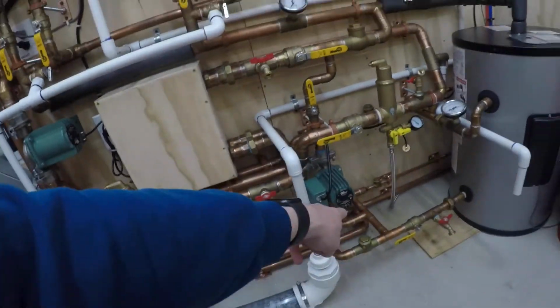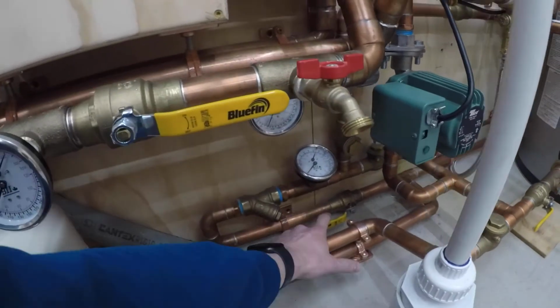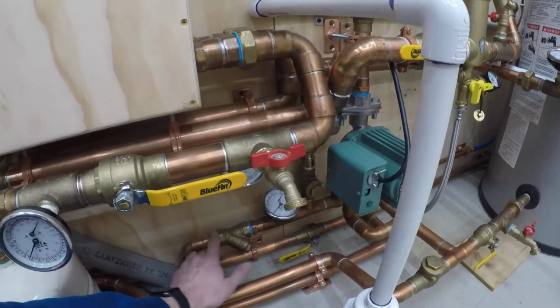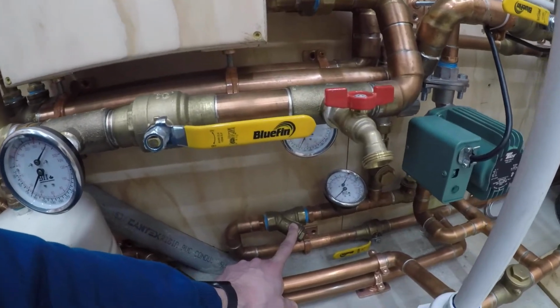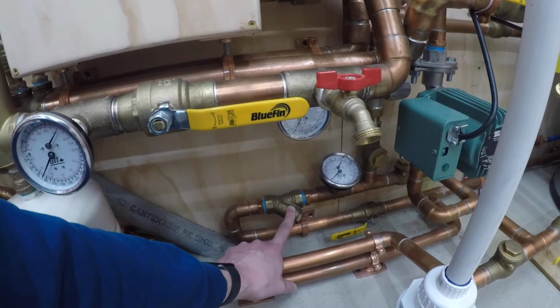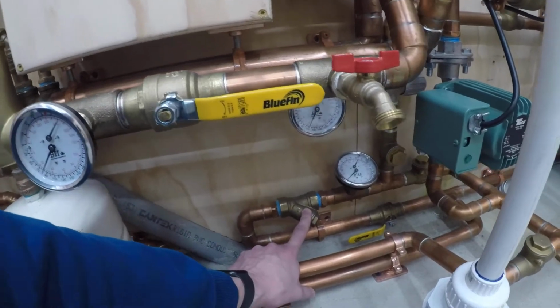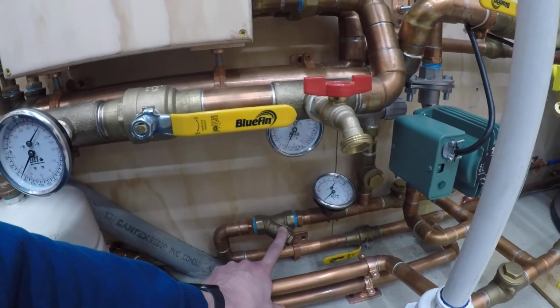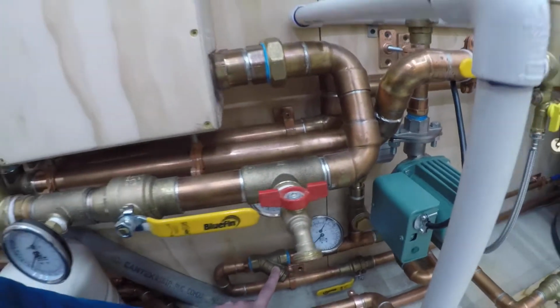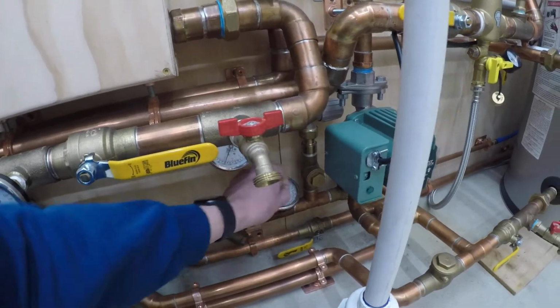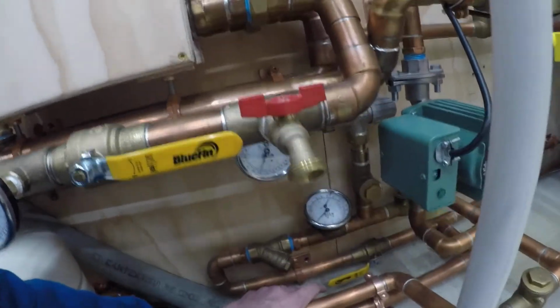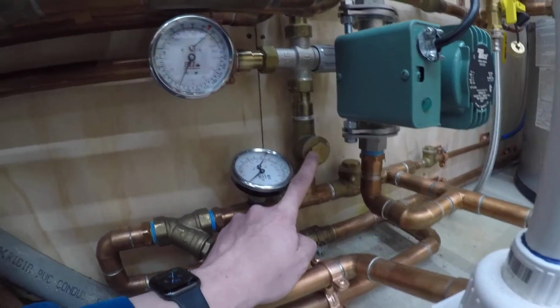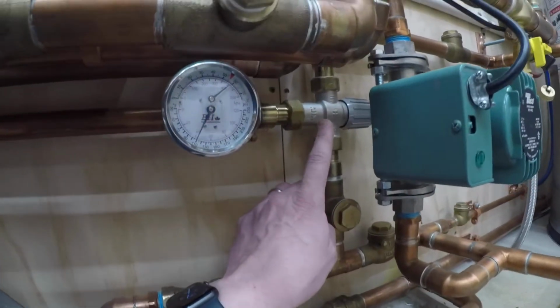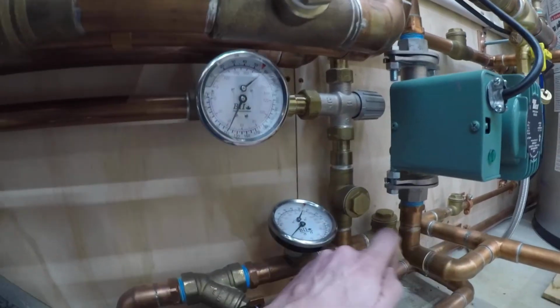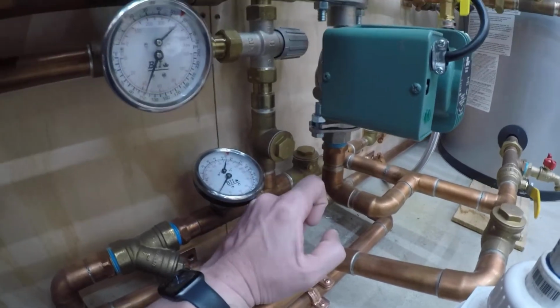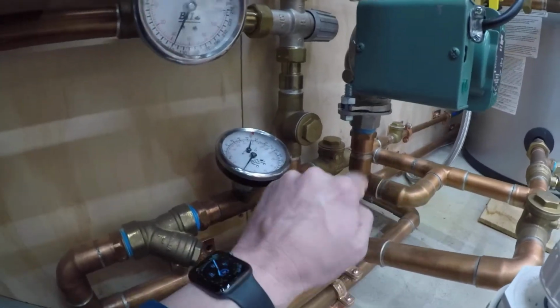Now what happens back here after this tee is it goes into a shut-off valve, around here into a strainer, just to keep any garbage that might come in from the street, which is kind of doubtful, but it's a cheap addition. It keeps any crap out of the hot water side of things and out of those tankless units. Then there's a pressure and temperature gauge here so I can see what the temperature and pressure is. Then we've got a one-way swing check valve that goes up to a three-way mixing valve, which goes out to my domestic hot water, and I'll get to that in a second. We have another one here that lets cold water into the hot water system.